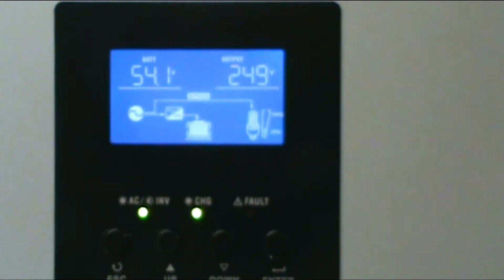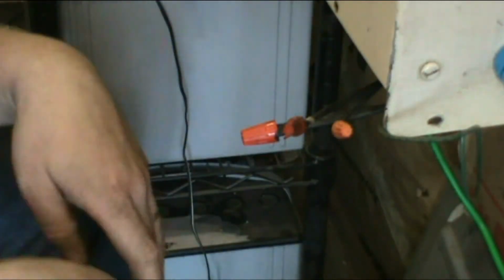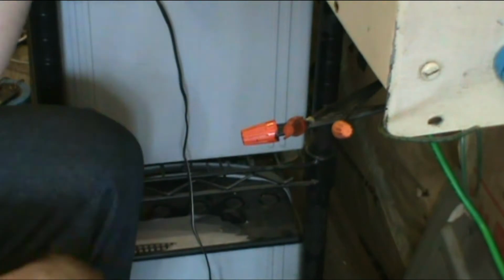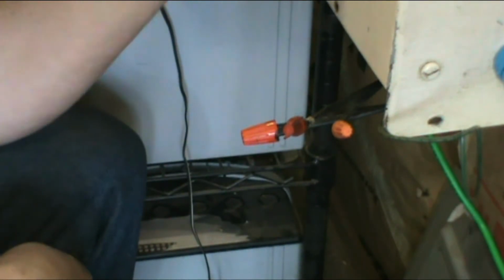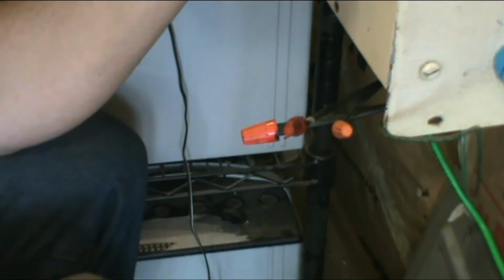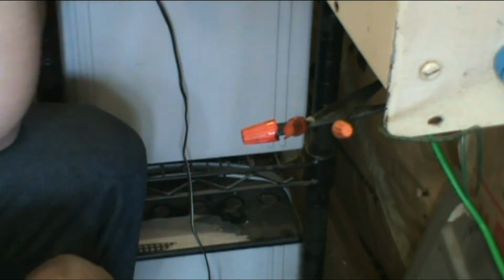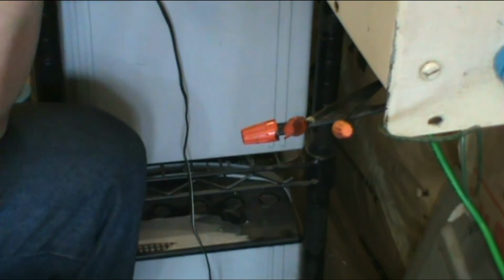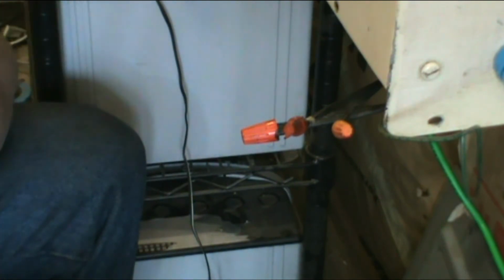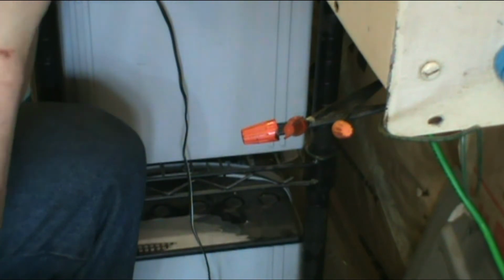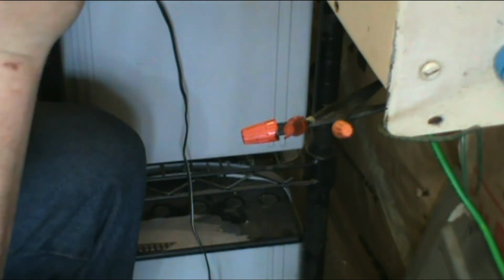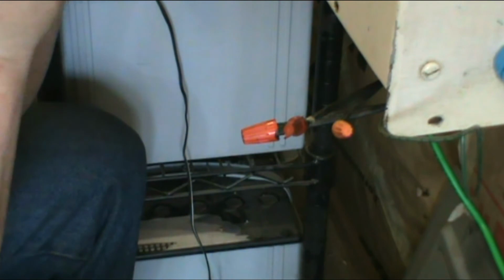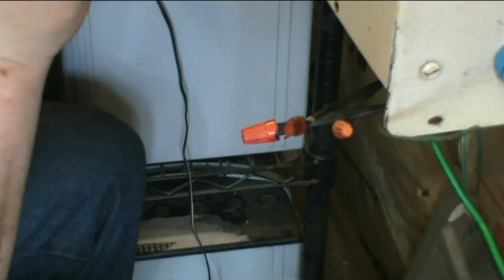Alright, here you go. We're down to the small transformer. You might be able to hear a small hum through it. I've got it hooked straight to the PIP. The PIP is running right now. I'll show you all that stuff. I did fire it up. When I'm done testing stuff in cycles, I tested the 7.5 kVA to make sure it's good. Got it hooked to the PIP. Got a temporary 50 amp breaker on the PIP right now to liven it up so I can get everything programmed.